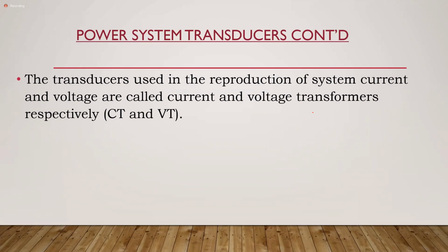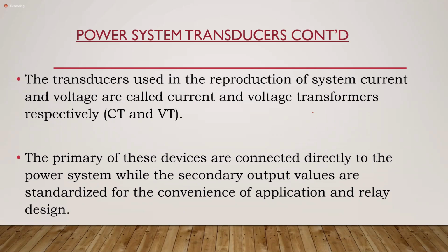So I've sort of touched on this already, but for transducers that produce your system current and voltage, for the current, it's your current transformer, and for the voltage, it is your voltage transformer. The primary of these devices are connected directly to the power system. And then the secondary, which are standardized values, and that's for convenience, are then fed into your relay.